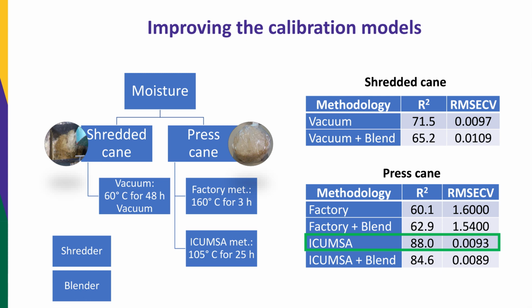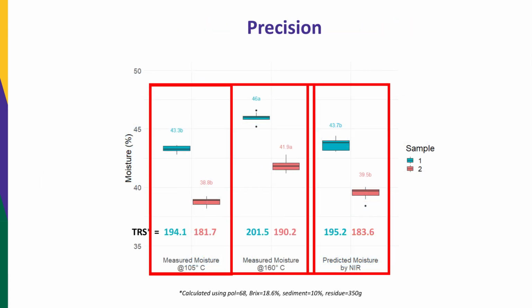We are getting better results with pressed cane if we use the ICUMSA methodology, if we dry the samples at 105. Why? Because as I showed you, that methodology is more reliable, and therefore we are getting better calibration models in the NIR. And now we move from 60% in the R square with the previous methodology to 88% using the ICUMSA methodology. So this is promising right now. I'm happy with this result because in other countries, they are already using NIR for moisture and they are getting good results. And now this is just proving that the NIR could be used for moisture analysis too.